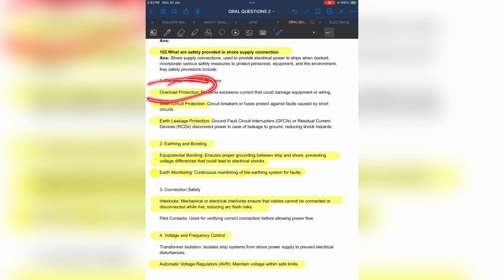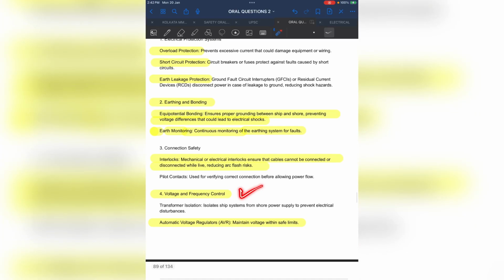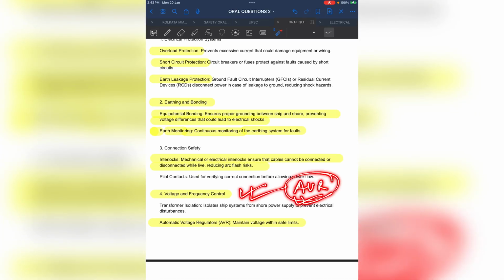So what protections do we use in a shore power connection? Overload protection, short circuit protection, and earth leakage protection. Earthing and bonding is also there in a shore connection. And after that, voltage and frequency control, the AVR, is there to control the voltage and frequency. These are the protections we are using.